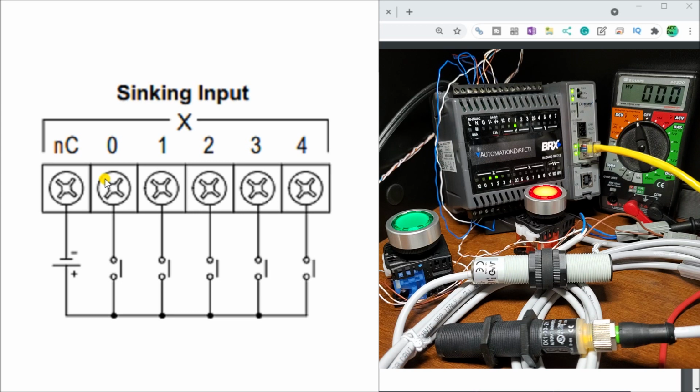The common practice is to have the entire PLC either sourcing or sinking. However, you can mix and match. So again, documentation is very important. And most modern PLC manufacturers will have sinking and sourcing inputs. This will determine how the common point for the input is wired to the supply voltage. And check the manufacturer specification for wiring to ensure that this is the case.